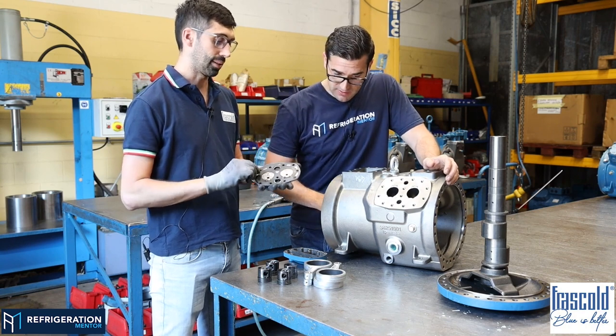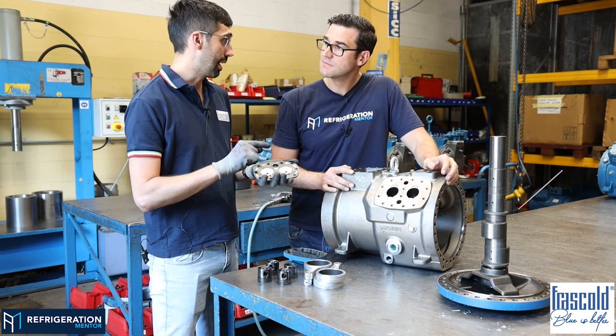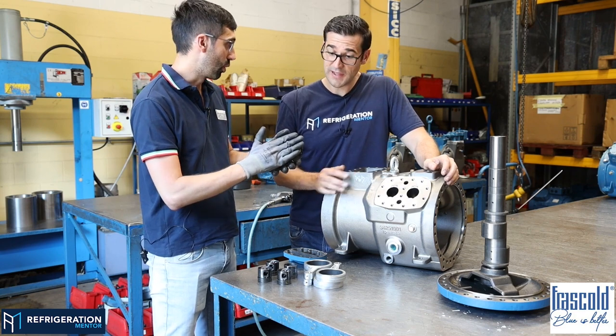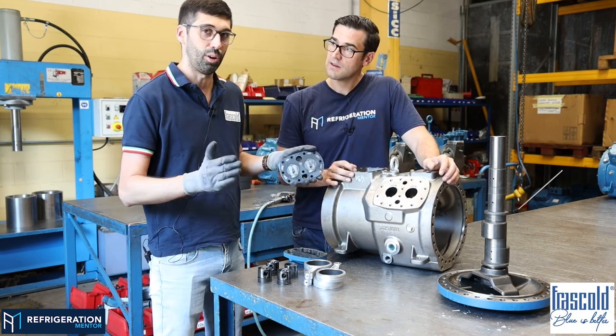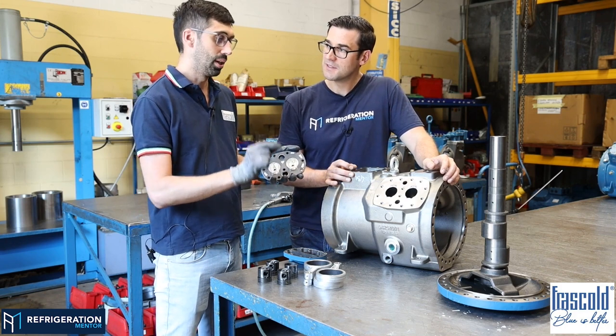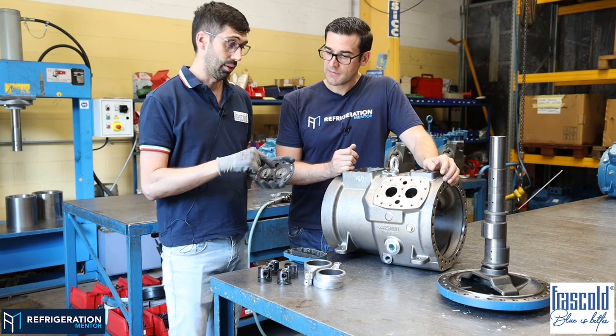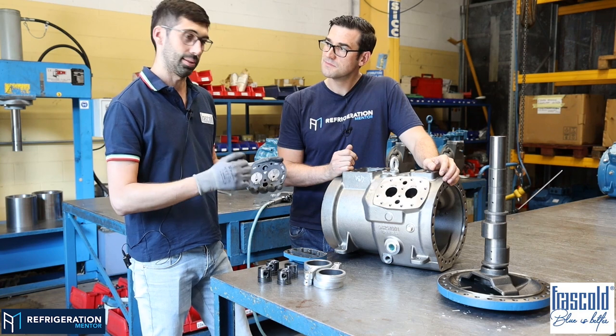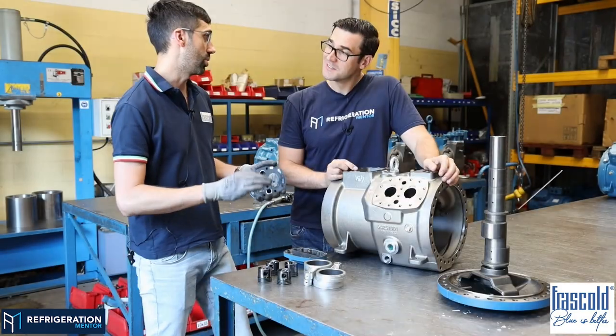We have the massive flood back, simply an unexpected, incompressible media inside the compressor chamber. So the very little gap, the clearance volume, we design with our technicians in the technical office is no longer there because it's totally filled by the incompressible film of liquid, and we are striking a punch directly to the reed valves, and we then face the breakage and the hammering of the debris between these two surfaces. So all of these components must be changed and replaced.